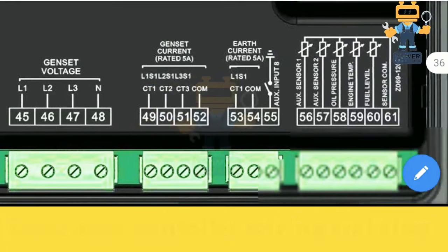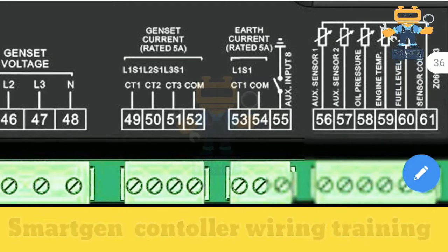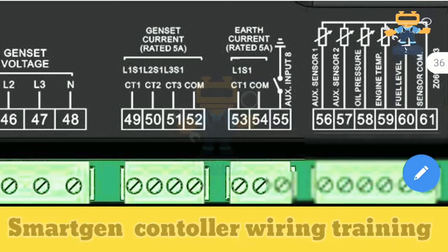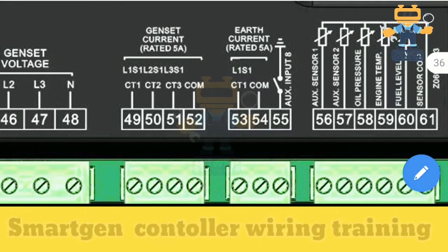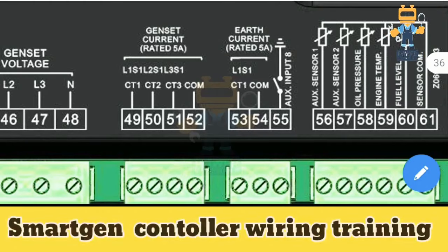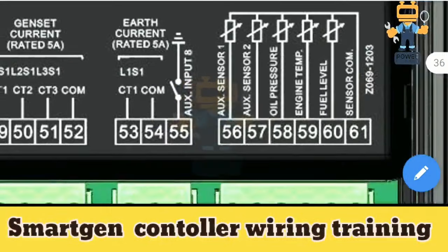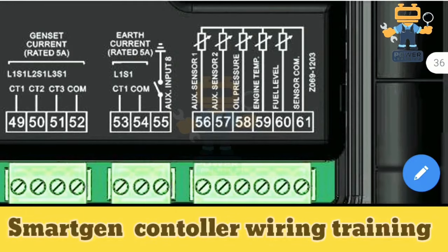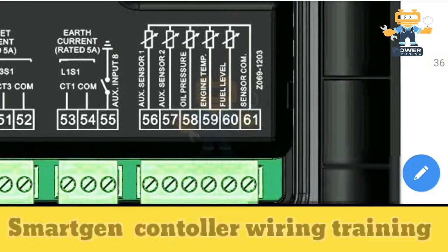Genset current is rated 5 amperes. Current transformers installed on the load cables of the load breaker measure the current and feed it back to the controller, which then displays kilowatts, kVA and amperes being consumed from the generator. For earth current, also rated 5 amps, if you are using an earth CT for earth fault protection you connect it on terminals 53 and 54, and the auxiliary input is at terminal 55.